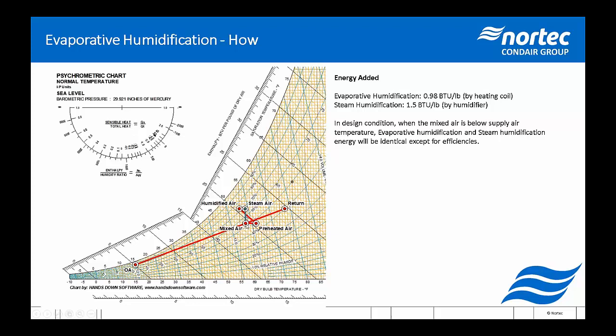So when we boil the water, you can see we go straight up. So we don't affect the air temperature when we're boiling water with steam, or humidifying with steam, excuse me. And we end up at a point pretty much directly above our mixed air point. However, if we're using an evaporative system and we don't have any additional heat to use, waste heat, etc., then we will need to preheat in this situation.